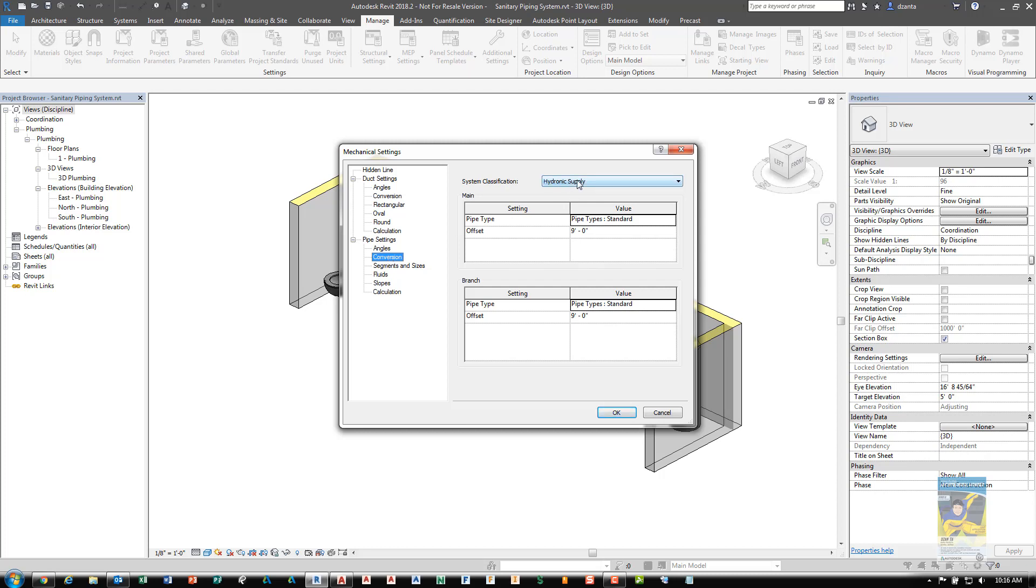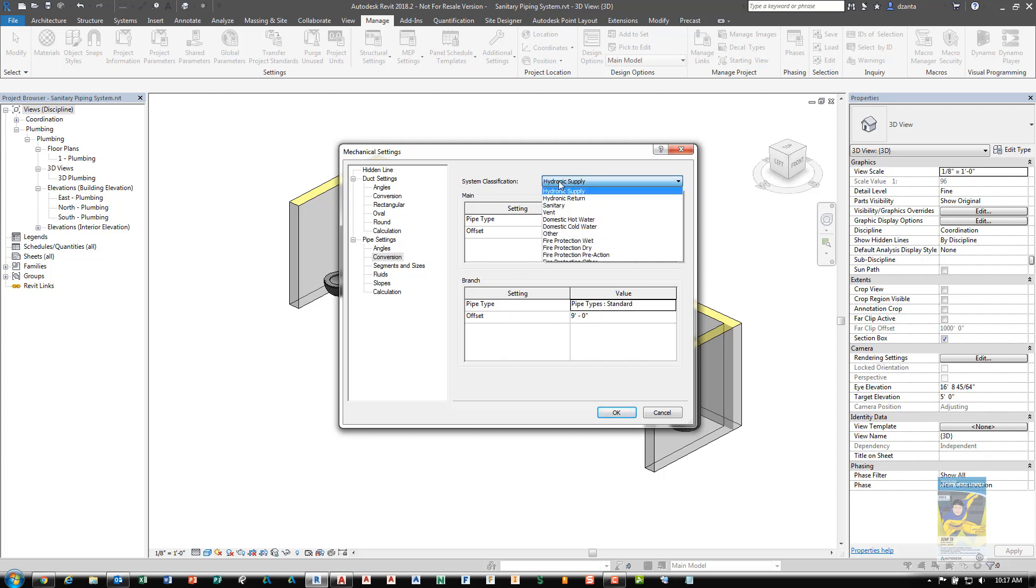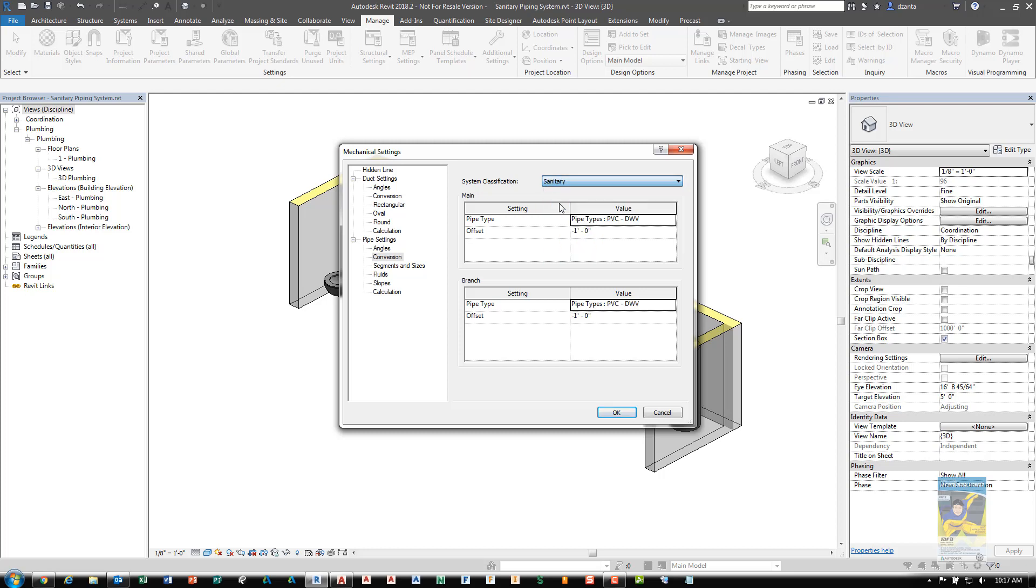In Conversions, you'll want to set up for the main branch and branch system what type of pipe to be used and what is its original offset height off of the level. Since we're creating a sanitary system, I'll switch this to sanitary and put in here a negative one foot for now. This can be any height that you want. Just think about that from the design standpoint.